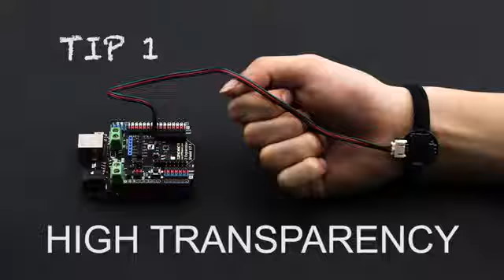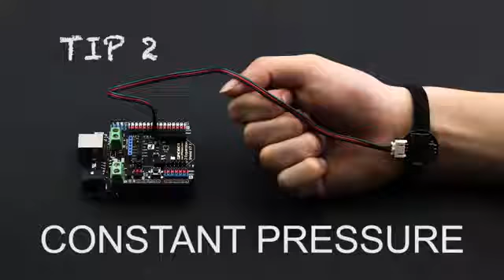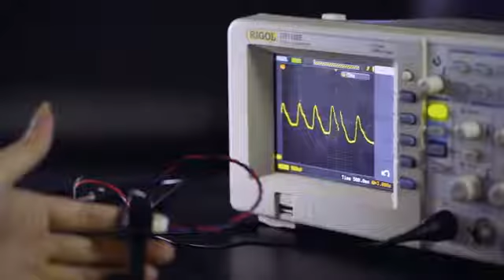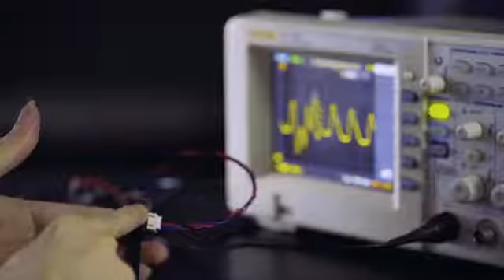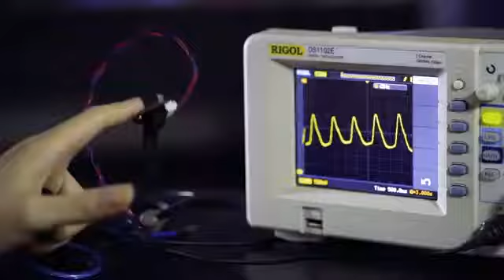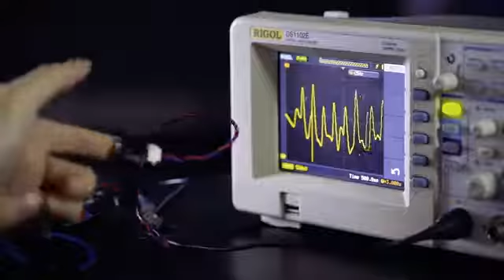Tip number 1. Stick the sensor onto an area with higher transparency, so the sensor will be more sensitive to the pulse change. Tip number 2. Stick the probe on the skin with a stable pressure. Any change of their relative position may affect the intensity of the reflected light. Remember, a blood pulse can be generated by other factors, such as instant body movement or simply a press on the surrounding skin. Tip number 3. Make sure the body is still during the measurement. Or put the sensor in a place that is less likely to be affected by limb movements, such as the chest or forehead.